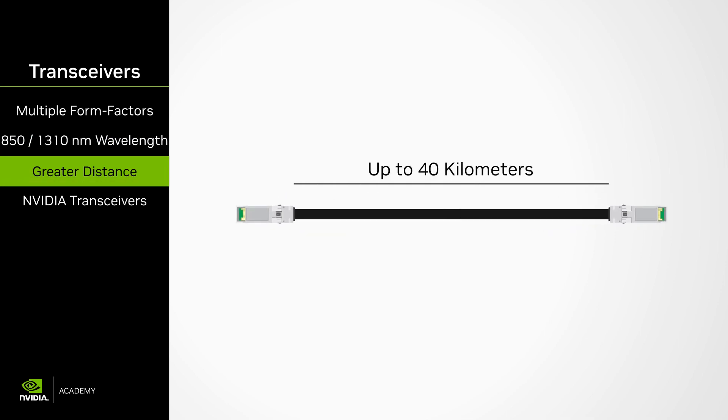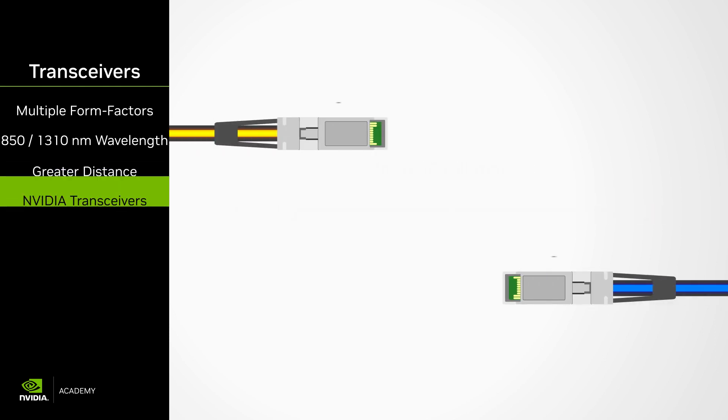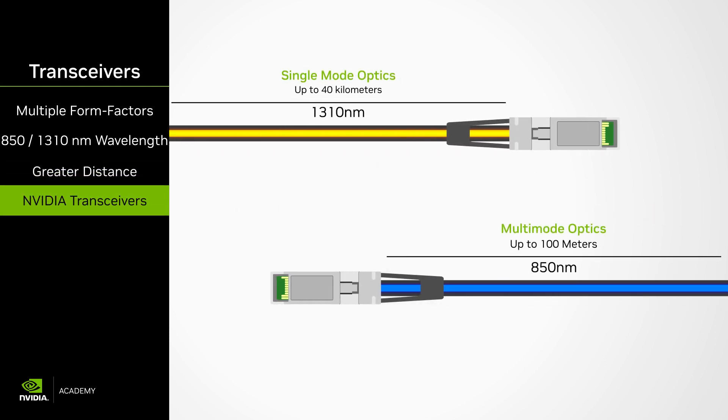Single-mode fiber keeps the data pulses neatly arranged and is used by the telecom industry to link San Francisco to Hawaii. In data centers, it's used to span entire data centers and link campuses together. Multi-mode optics is much less expensive to deploy, but the data signals scatter, limiting the lengths to 100 meters. It's used predominantly to link switches together.